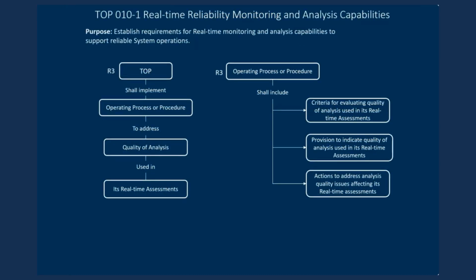TOP 010-1, requirement 3, says the TOP shall have operating processes and procedures to address the quality of analysis that are used in the real-time assessments. This primarily refers to the contingency analysis software. So the contingency analysis software is looking at all the different single contingencies and double contingencies and giving you voltages as well as line overload conditions.